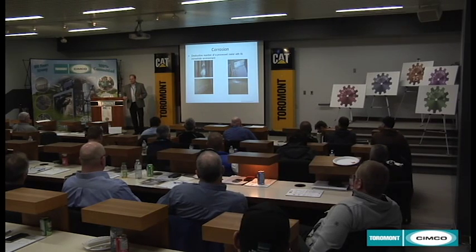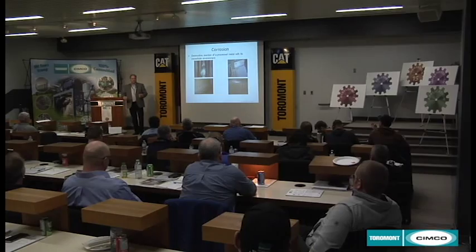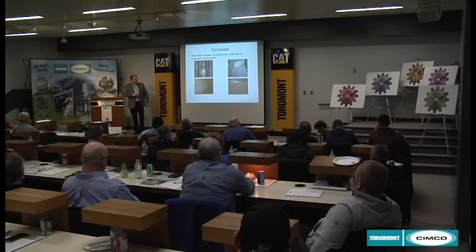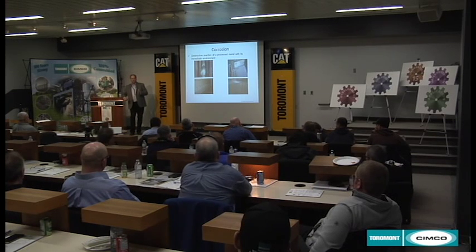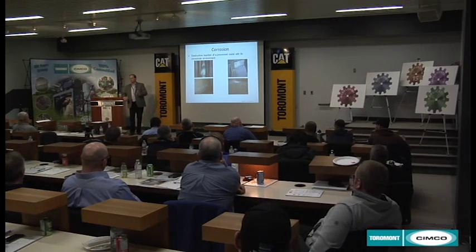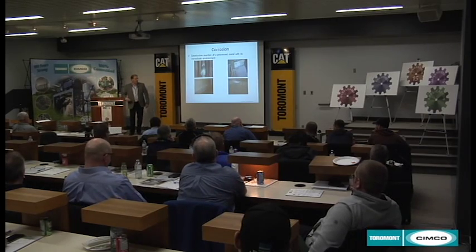What we call white rust is the effect of having a higher pH in the water going through your cooling tower, and also not having the right water treatment control in the cooling tower. Right there is called white rust. Those little white nodules on that galvanized surface are called white rust. It's the effect of zinc basically falling off the metal surfaces and exposing them to potential corrosion.